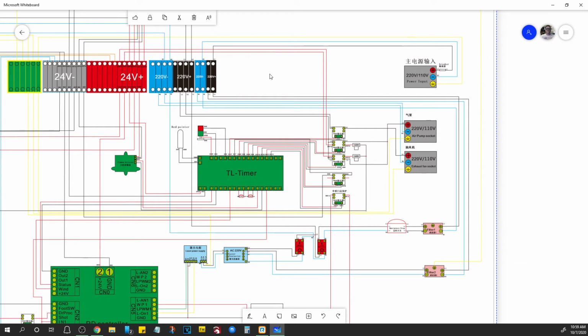So the points that you need to check are all the terminations. Make sure that the wires are tight. Give them a little pull. Make sure you unplug the machine before you go working in there and looking at things. You want to unplug it and ensure that the system is not energized. So check your cords, check your terminations, come over here, check your screw terminations.